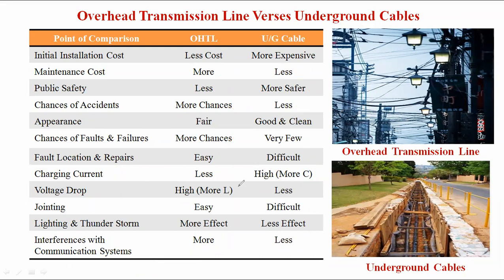Voltage drop: in overhead transmission lines the voltage drop is more due to inductance; in underground cable the voltage drop is less. Jointing of conductors in overhead transmission lines is easy — using the same aluminum conductor material, we simply twist the conductors. But in underground cable, jointing is very difficult. With the help of clipping and bolt-nut, we need to join the conductors, and as the operating voltage increases, the core size increases, making jointing even more difficult.